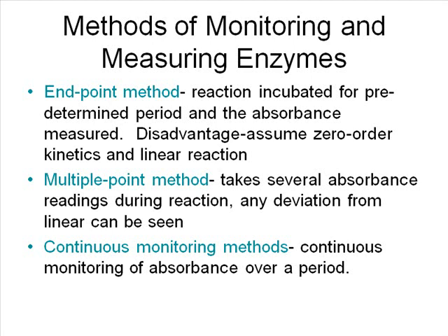Then it comes back to that cuvette and the spectrophotometer starts measuring. Because as it's measuring, remember, the absorption level may be going up if you're measuring hydrogen, for instance. So then what it does is it measures that rate of absorption and converts it to your enzymatic value.